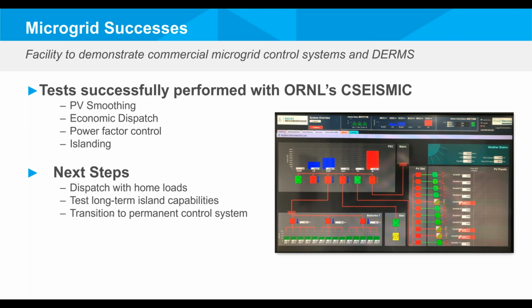And next steps, we're looking to dispatch the home loads, essentially creating virtual power plants in a way, because with the smart home appliances there'll be some load shifting, especially for the HVAC and water heater. And on the microgrid side, we're looking at ways to use the energy storage to provide benefits to the grid. Next, we're looking at testing long-term islanding capabilities of the microgrid. We have solar, energy storage, and a backup gas generator. The objective here is to see how long we can have the microgrid carry the load without power from the grid.